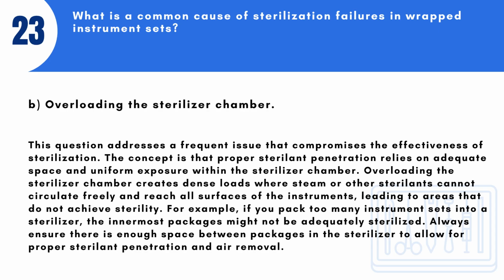This question addresses a frequent issue that compromises the effectiveness of sterilization. The concept is that proper sterilant penetration relies on adequate space and uniform exposure within the sterilizer chamber. Overloading the sterilizer chamber creates dense loads where steam or other sterilants cannot circulate freely and reach all surfaces of the instruments, leading to areas that do not achieve sterility. For example, if you pack too many instrument sets into a sterilizer, the innermost packages might not be adequately sterilized. Always ensure there is enough space between packages in the sterilizer to allow for proper sterilant penetration and air removal.